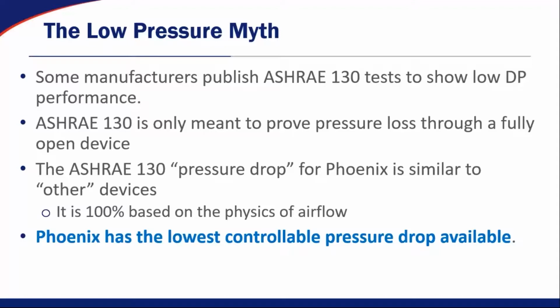And they're citing ASHRAE 130 as the low pressure performance test. Now, ASHRAE 130 is one of those things we were not familiar with. We had to educate ourselves on it. And basically what ASHRAE 130 is, it's a test that measures the flow through a device when it's fully open. So if you think about a VAV box, you fail the device fully open, so the blade is parallel to the ductwork, so there's very little obstruction in the ductwork. And then you put a pressure on the inlet side and you measure the flow coming out of it.